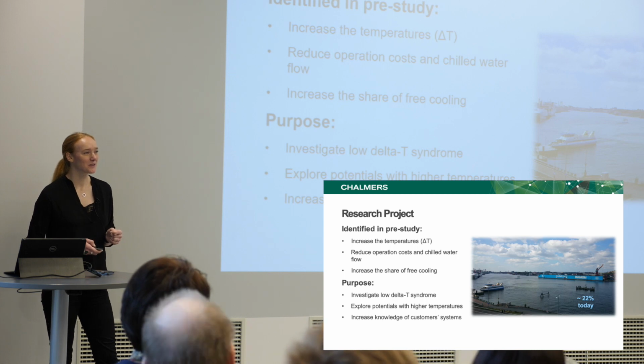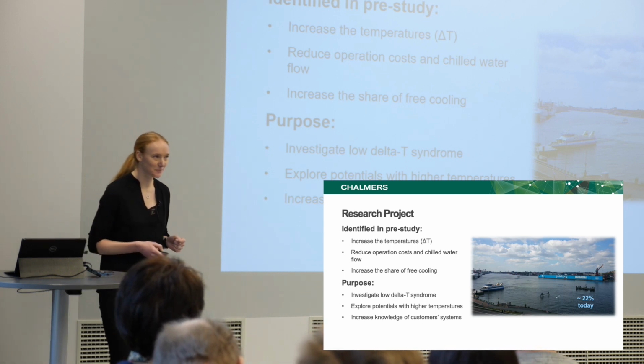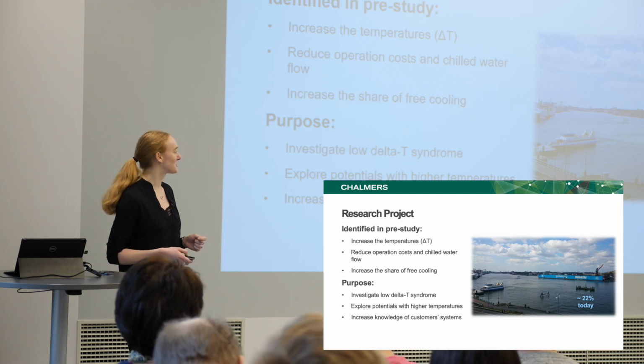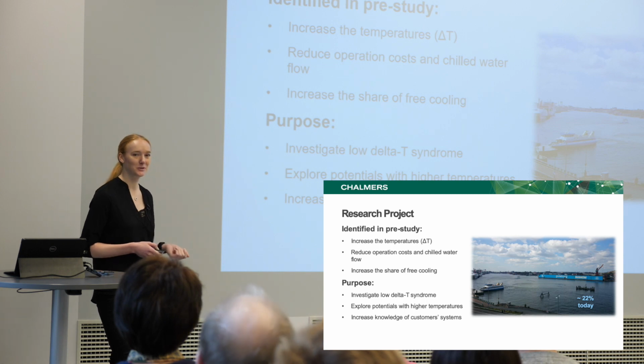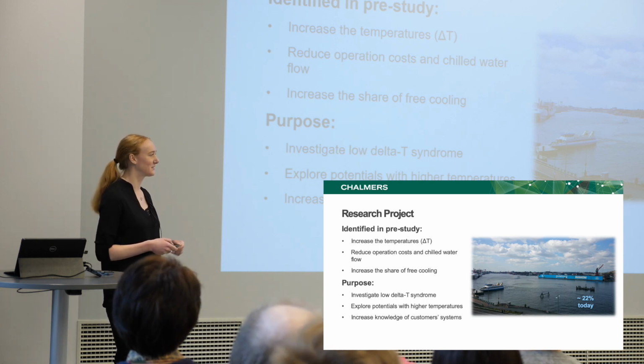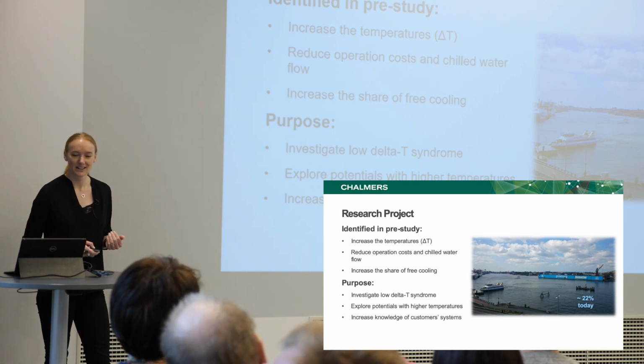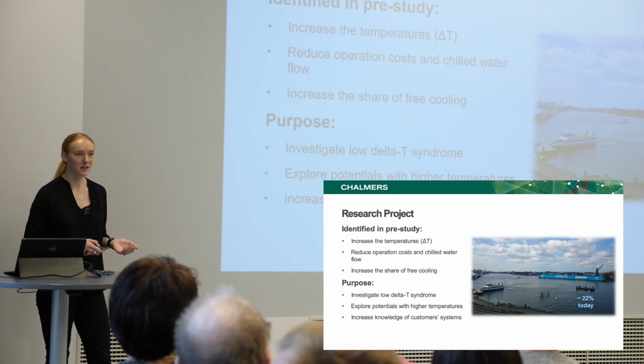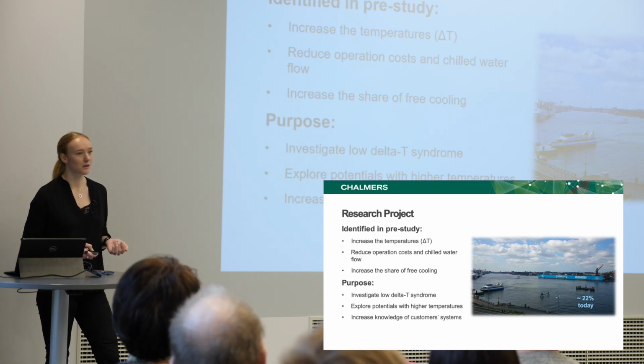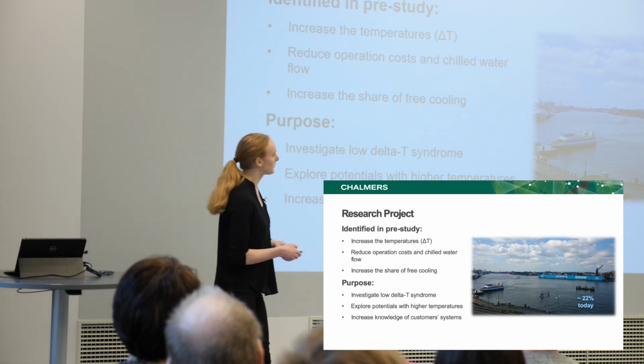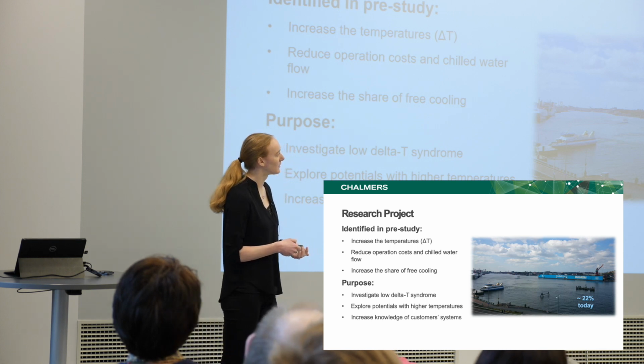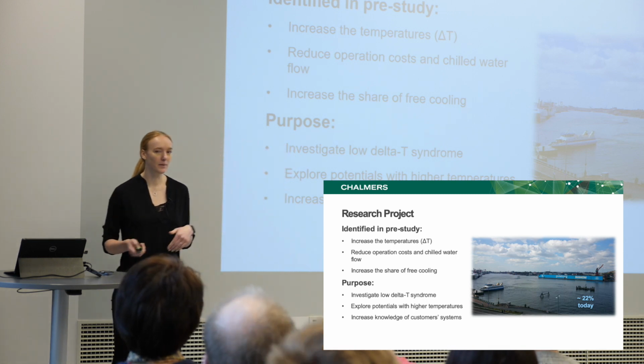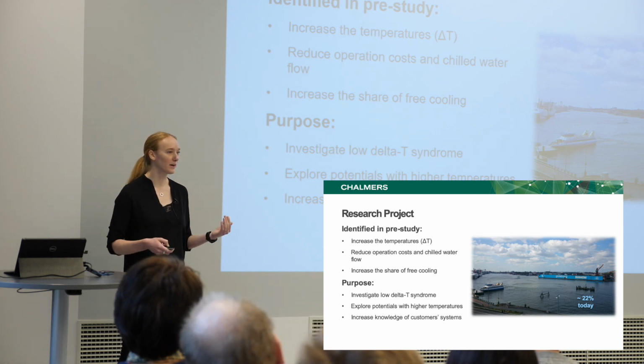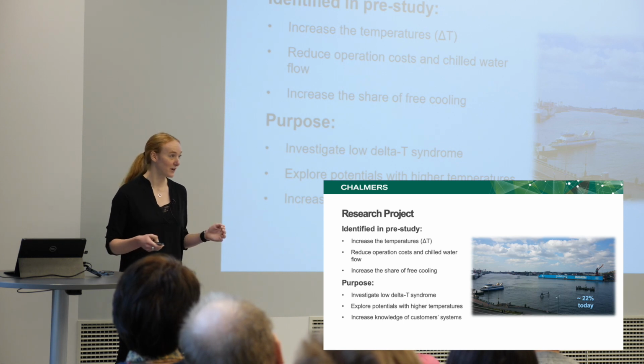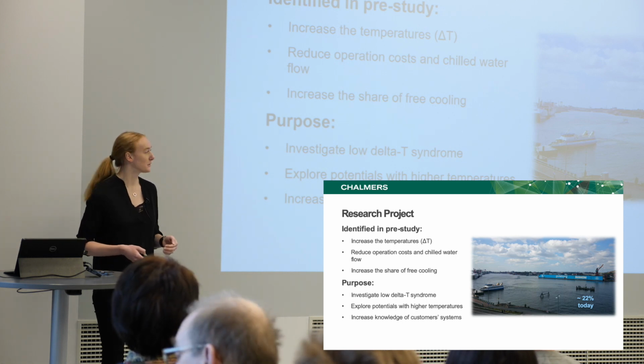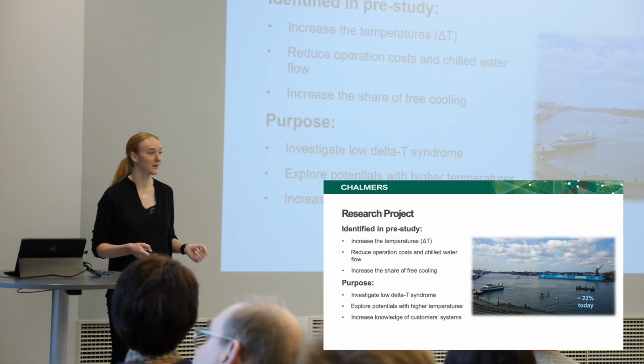So this brings us over to my research project. And in a pre-study done to my research project, it was identified that the temperatures can be increased, just what I showed you. They're not what they should be. They're not reaching the design temperatures on the return side. So with this, reduced operation costs can be achieved. And also the share of free cooling can be increased. So now you already know that the river is used for free cooling around 22% today. But with the combi operation, the river can be used more if the return temperature wasn't around 12 degrees on average throughout the year. If it was actually 16, the river can be used a lot more for free cooling as a total share of the year.